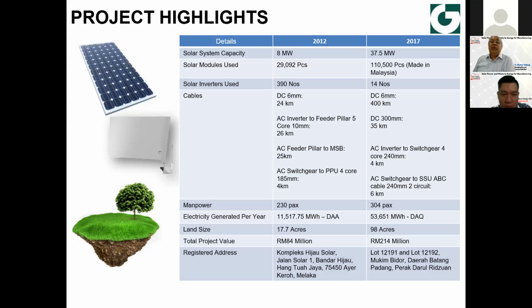In 2012, when we started using 390 pieces of string inverter, everybody laughed at us and said we were crazy because we'd have to maintain and service so many units. But over time people realized it was a very wise move. Why? Because if the system broke down, we would otherwise have had to bring in experts from Germany, Sweden, or overseas to repair it, and parts would normally take two months to arrive. Whereas using string inverters, we bought a lot of spares, so we just used a junior technician to swap and replace any faulty unit. As a result, we had zero downtime, no outage, in the 8 megawatt plant.